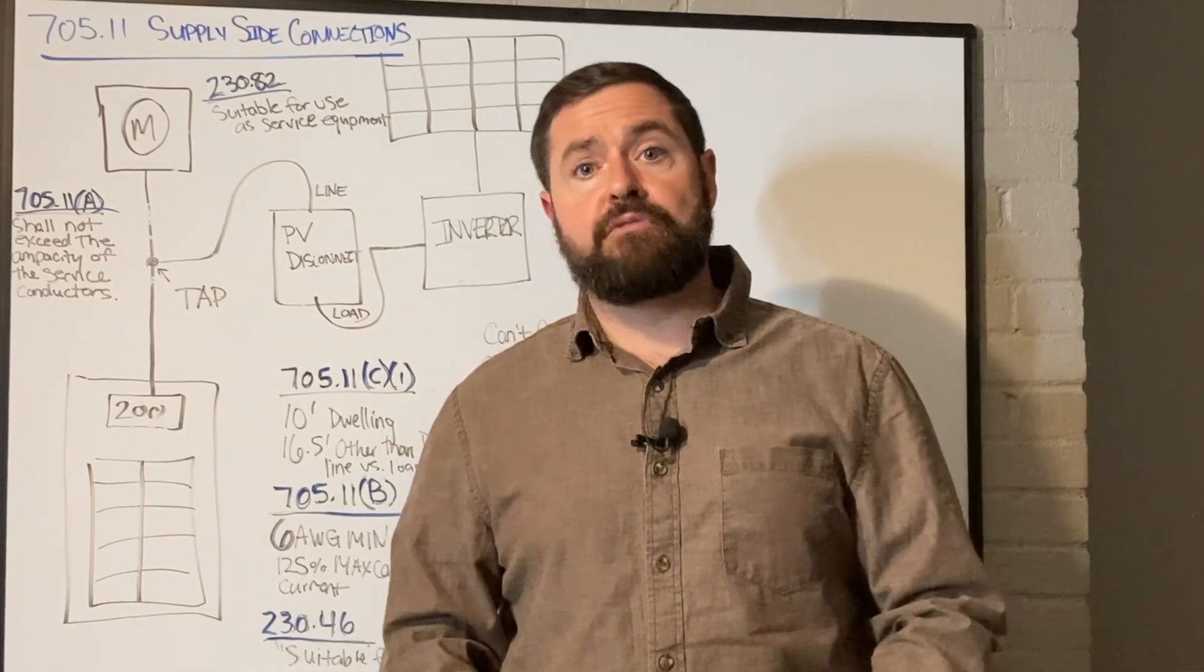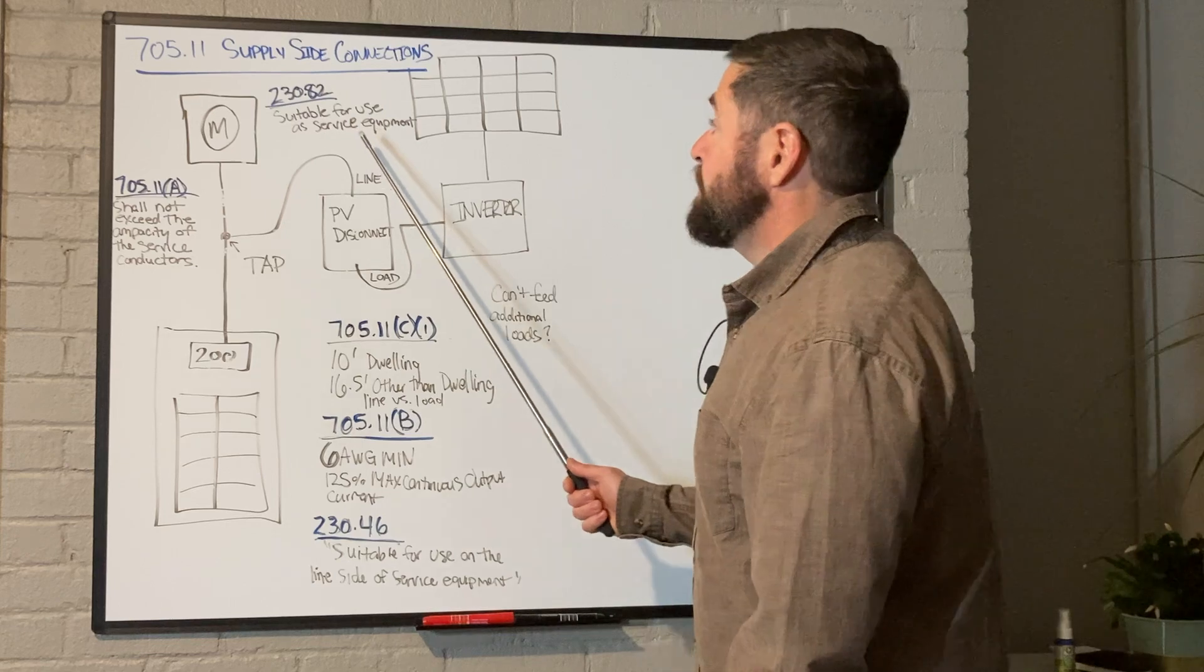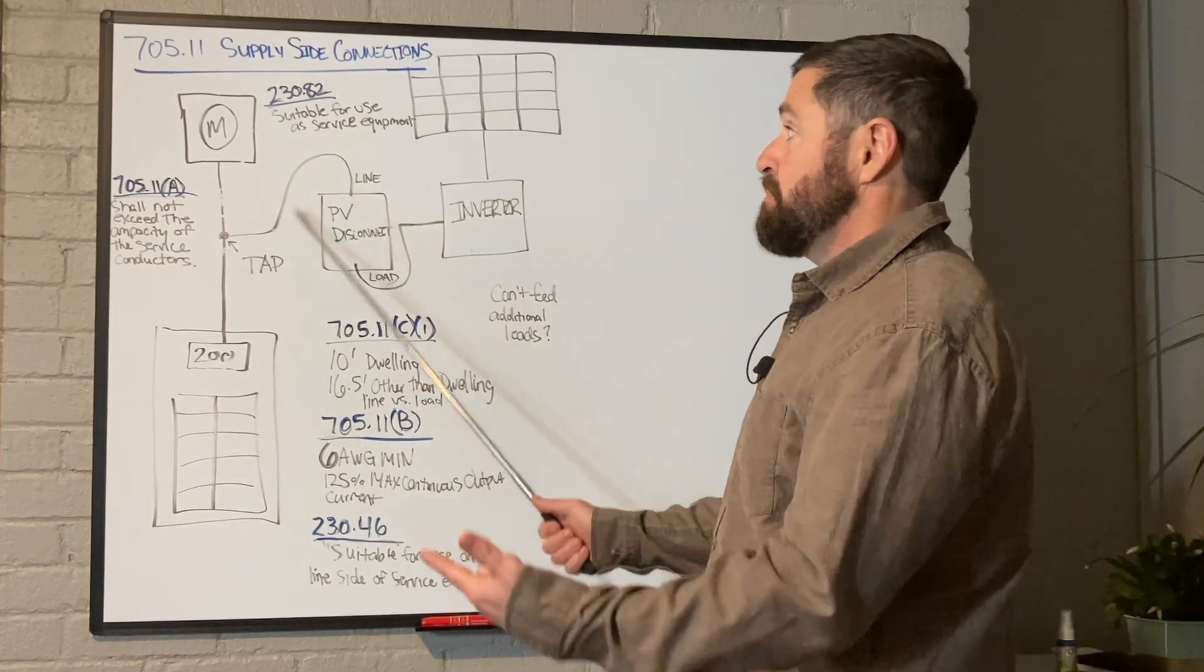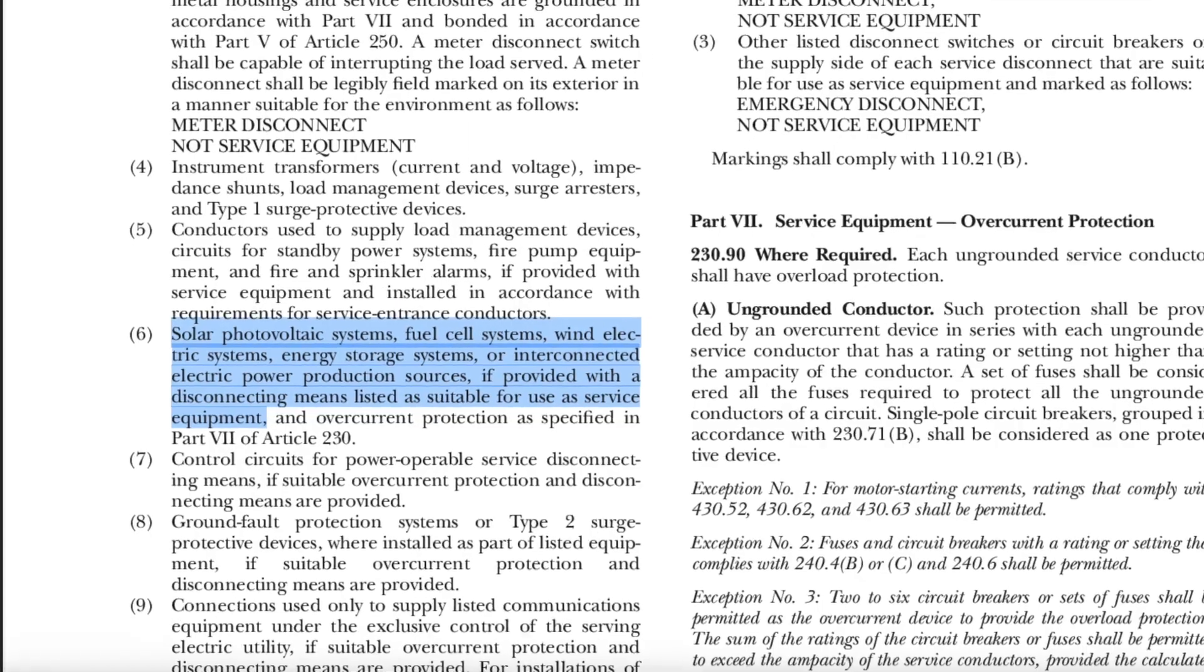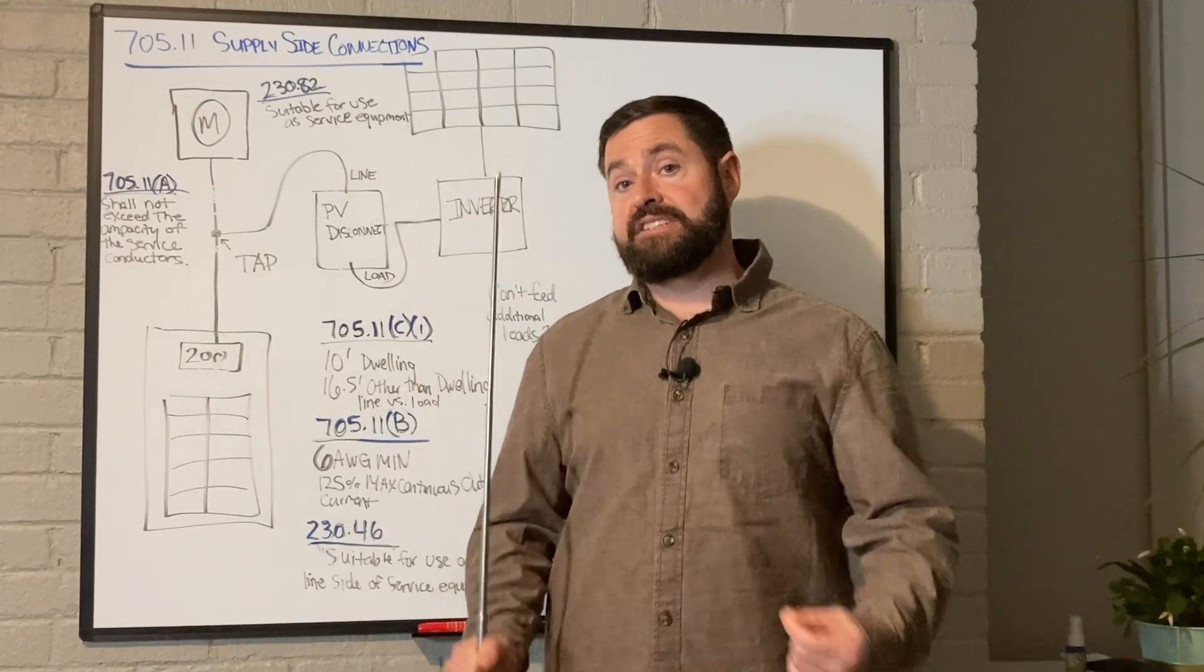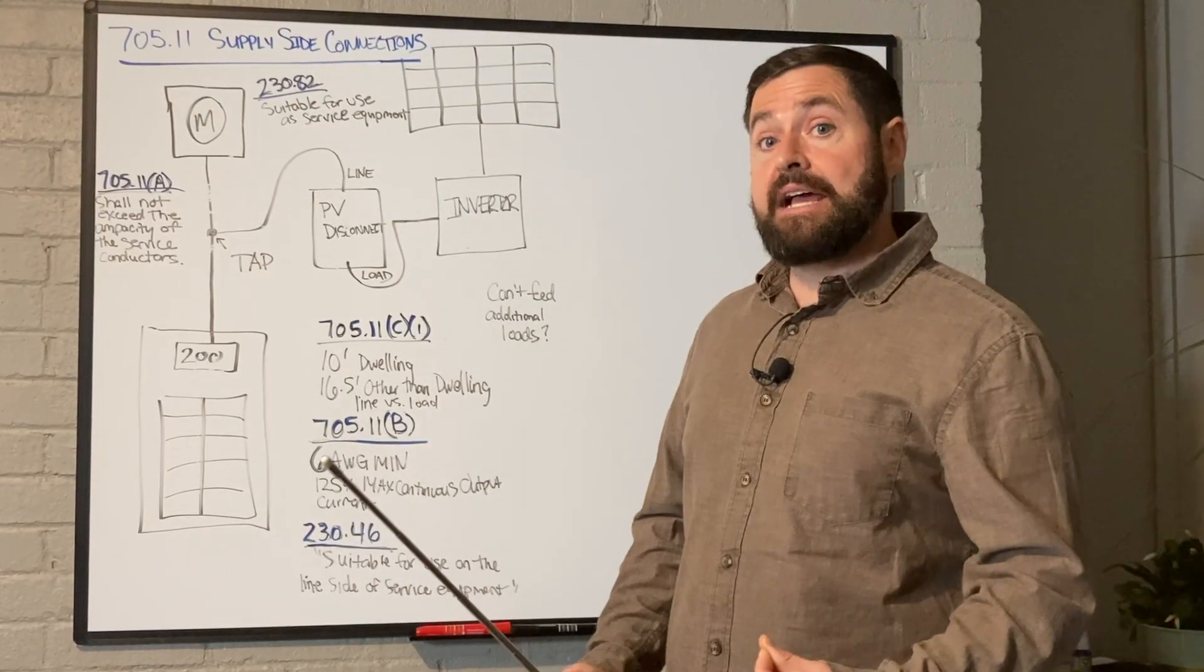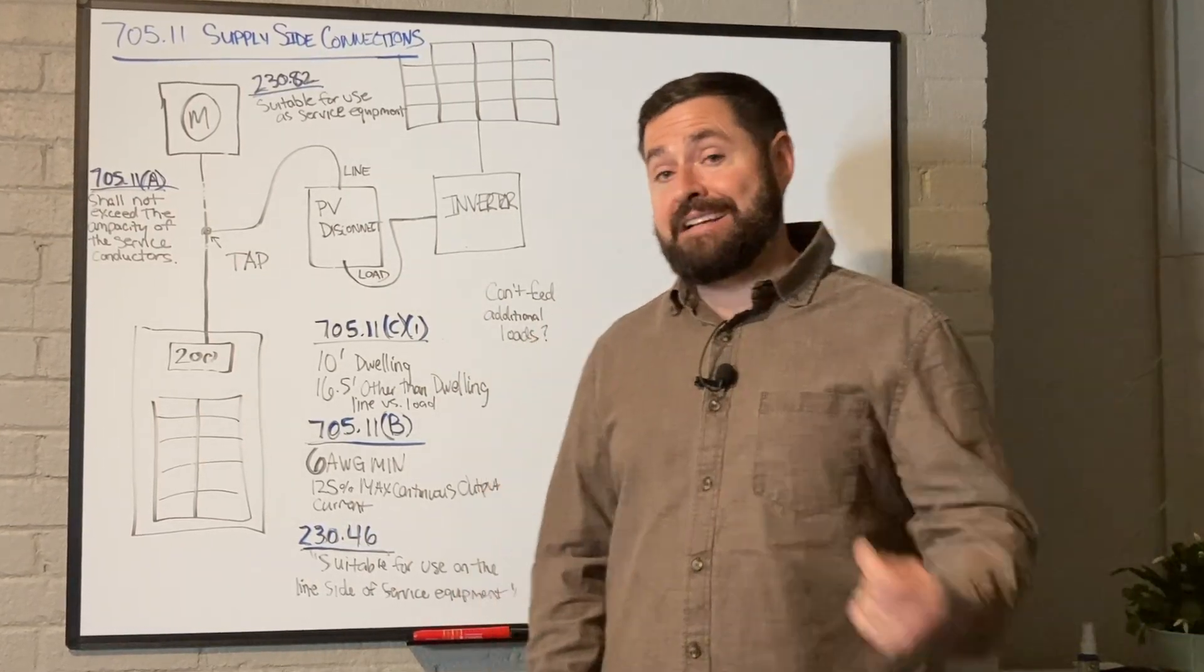So 230.82 is basically saying that PV system disconnect when used in a supply side connection needs to be suitable for use as service equipment. So to be clear, this is not defined as a service disconnect. It is a PV system disconnect. That being said, you essentially wire it up as a service disconnect.